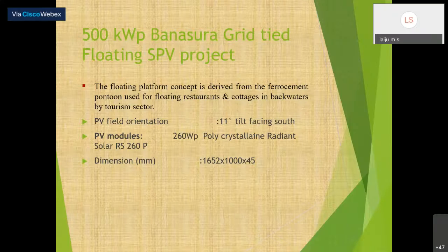So we have to design how to contour the panels or lay the panels on each float, how many panels can be laid, how the electrical wiring can be done, and how the electrical sizing of inverters can be made. During the DPR, the detailed project report time, we were thinking of only 2 inverters. And we planned to use a central inverter. Central inverter means an inverter which is housed in a room. That room is the SCADA room or the control room. So initially 2 central inverters of 300 kilowatt were selected. But depending on the site conditions, we change. Why are we going for such large inverters? Instead, we are thinking of whether it is suited.